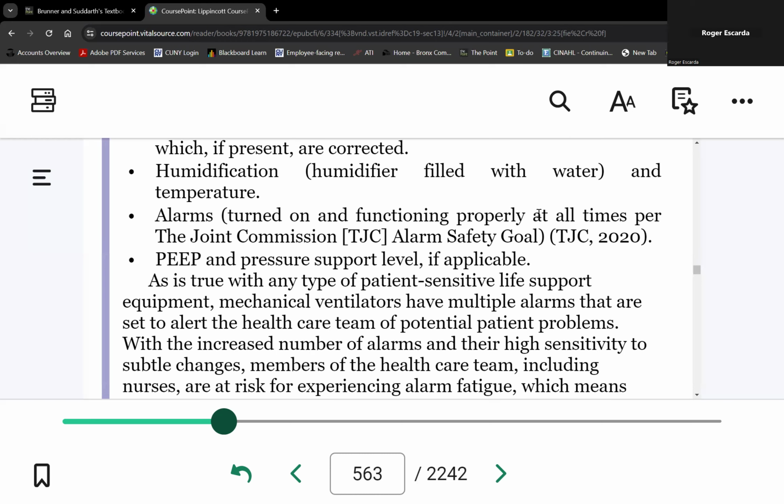Because there's no more breathing, there's no more resistance. The patient is not inhaling or exhaling, so the vent will sense there's no pressure, so it will trigger, all right? So these are the various alarms you'll have; again, we're only testing high or low pressure.